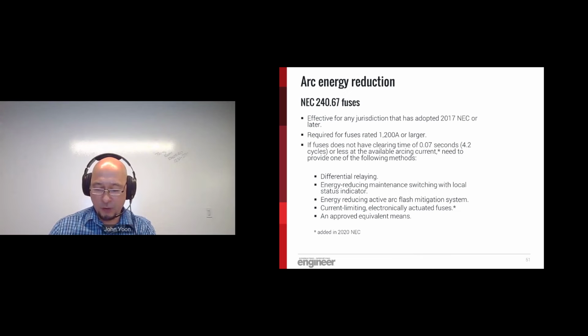So the code requires that we provide some type of arc energy reduction. And for fuses, that's for 1200 amps and larger, same as circuit breakers. If that fuse can clear an arc fault in 0.07 seconds or less, you don't have to do anything else, but that's dramatically harder than it sounds. Again, the minimum and maximum melt times for a fuse aren't adjustable like a breaker with a solid-state trip unit. In most cases, you're stuck providing some type of supplemental tripping device.